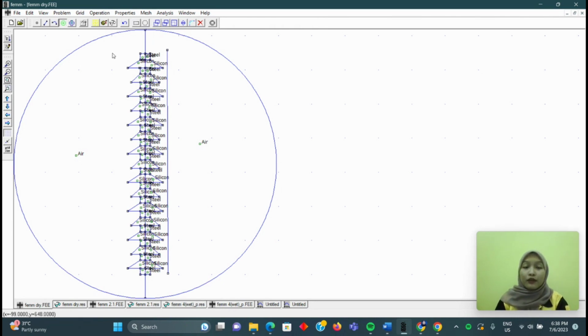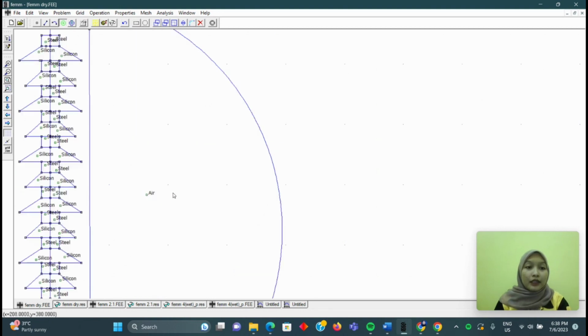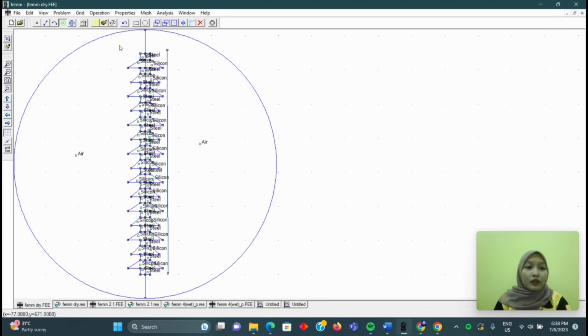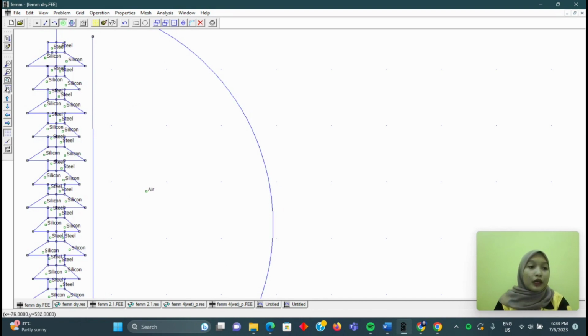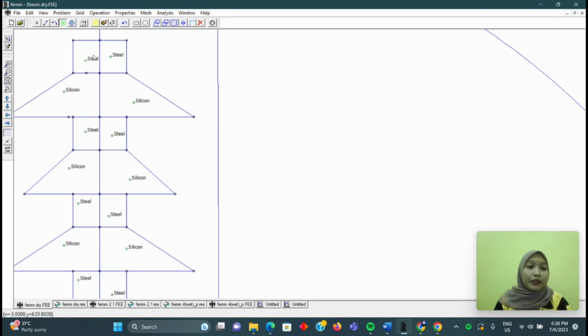As mentioned before, our group is the alternate shed type. Here, as you can see, for the insulator we have the big one and then the small one, and then a big one and then the small one. So this is what alternate shed means. For the insulator, we use the long rod type. The material we choose for the core is steel, and for the weather shed of the insulator is silicone.